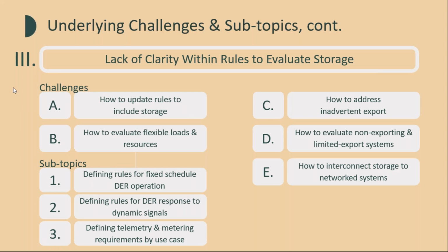Little in the sense that we're talking about a very small amount of export. This is one of the biggest little challenges on this list: inadvertent export, which can occur when a customer's system is sized too closely to match their load, or if a customer has a very large load, such as an electric vehicle, and that load turns off while it is drawing from the storage system. When this happens, the battery system inadvertently exports small amounts of power for very short durations when these unanticipated load fluctuations occur.